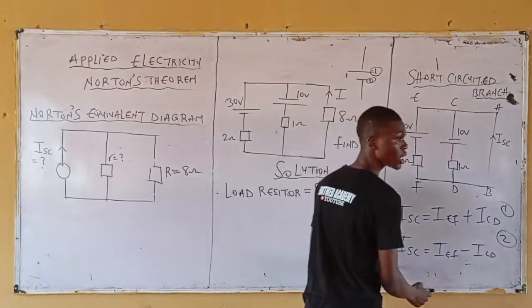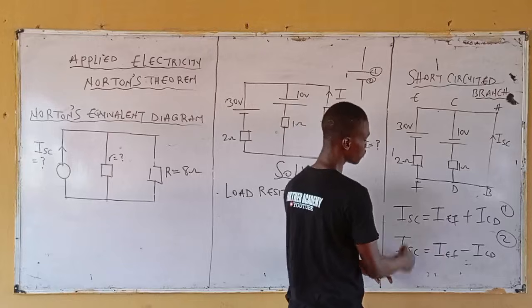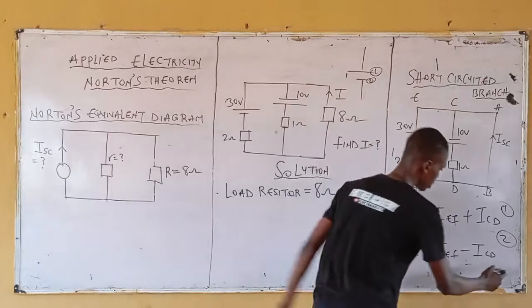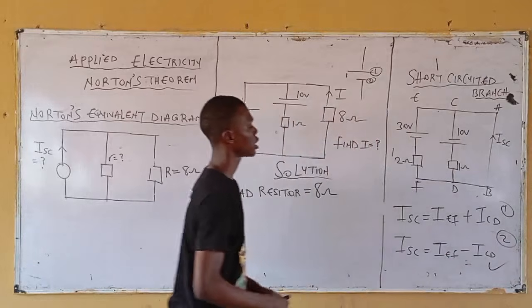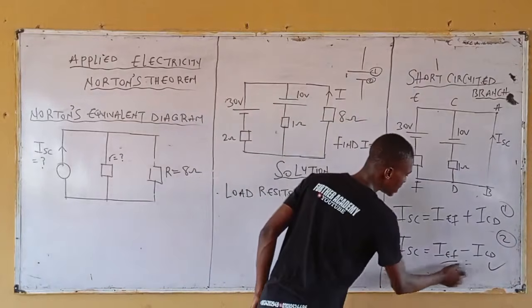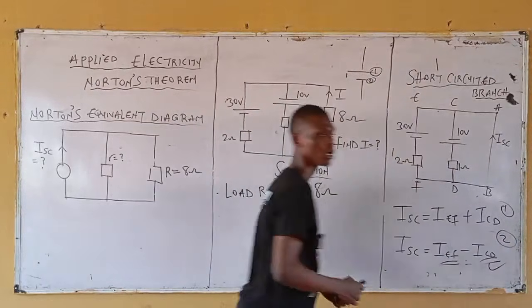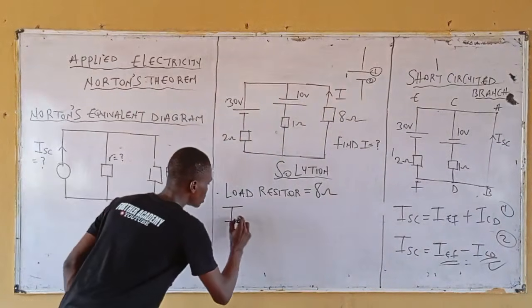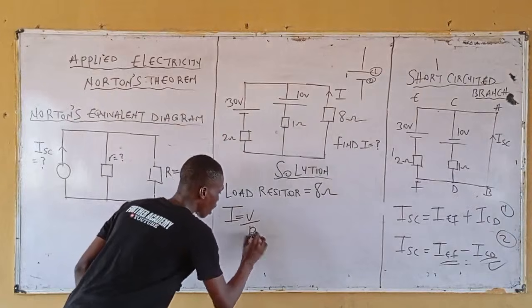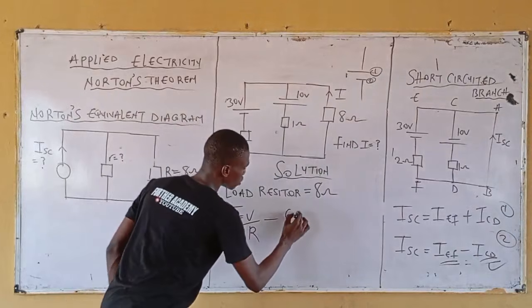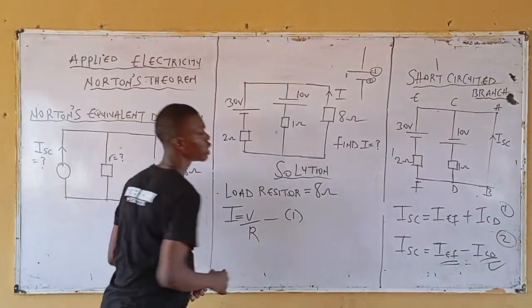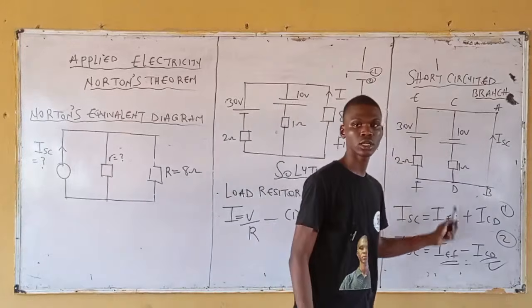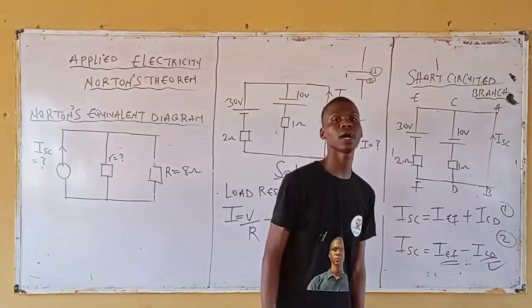Meaning the correct formula to use for I short-circuit is case two. This is what we are going with. Now, how do you calculate IEF and ICD? From Ohm's law, I equals V over R — call this equation one. Implementing equation one to branch EF and branch CD, you get IEF and ICD.